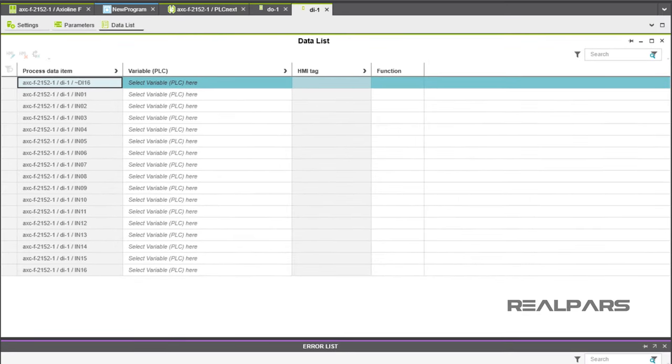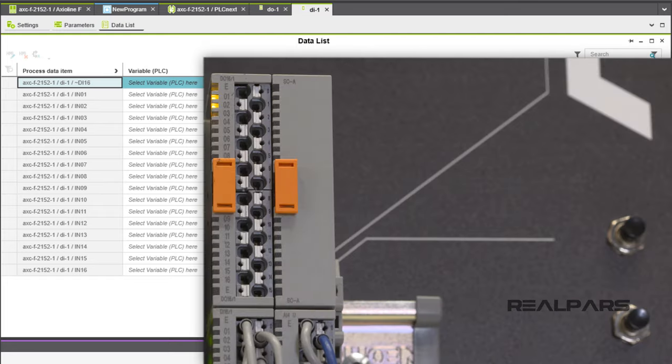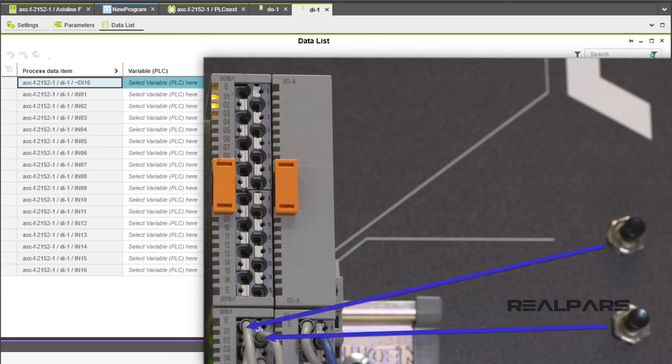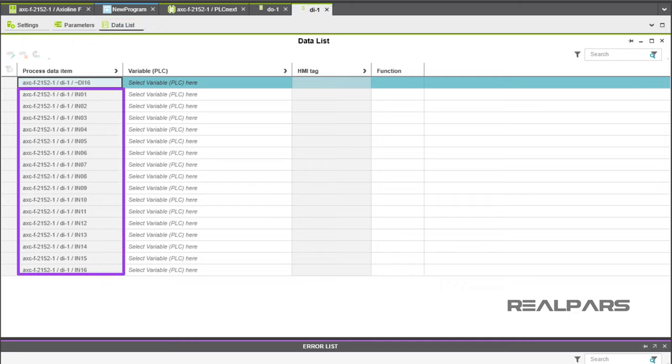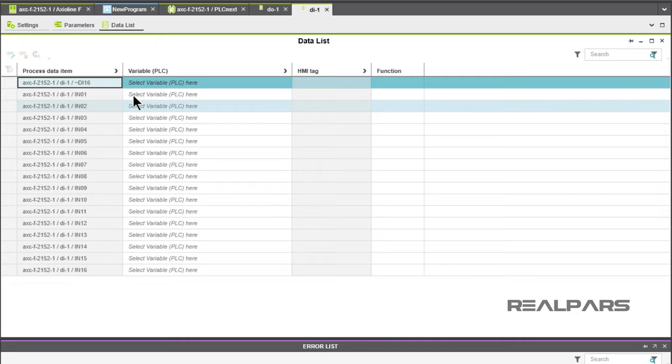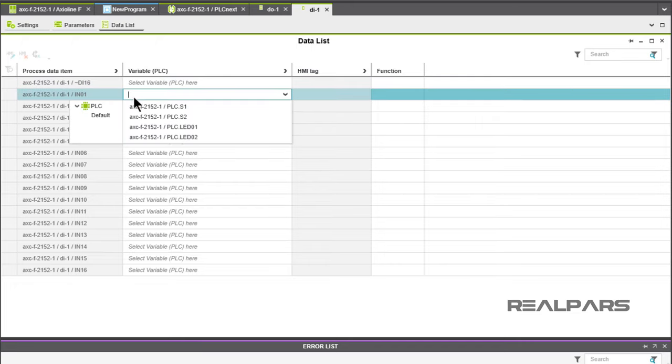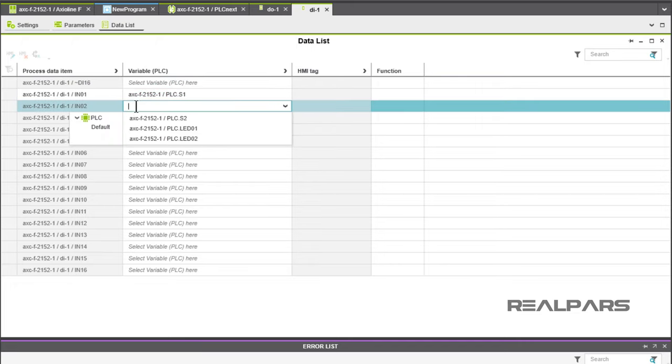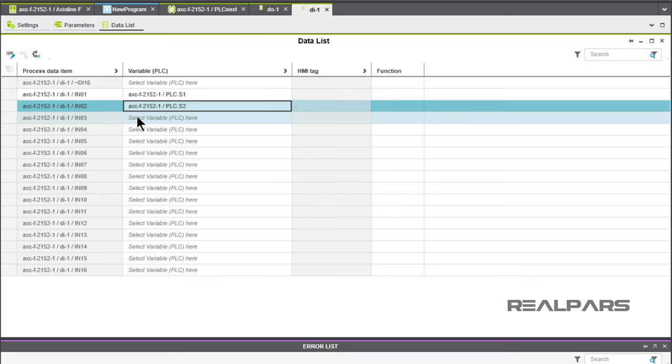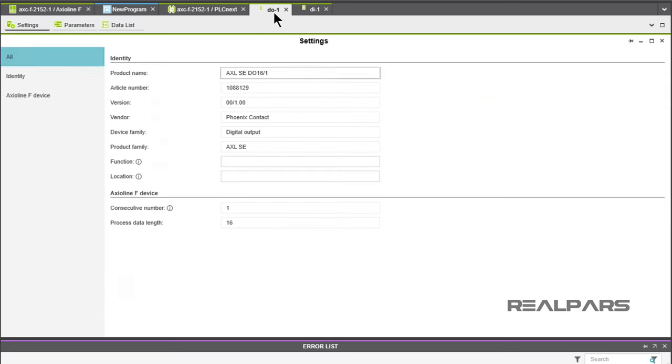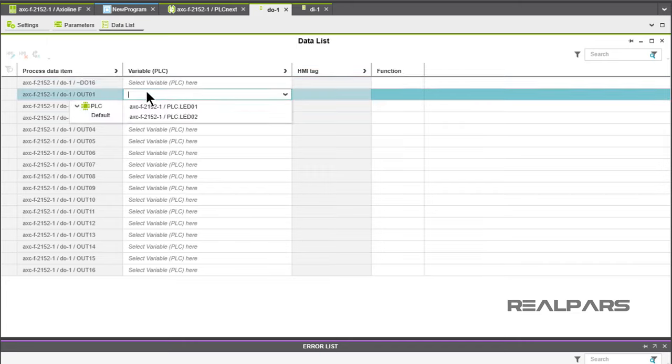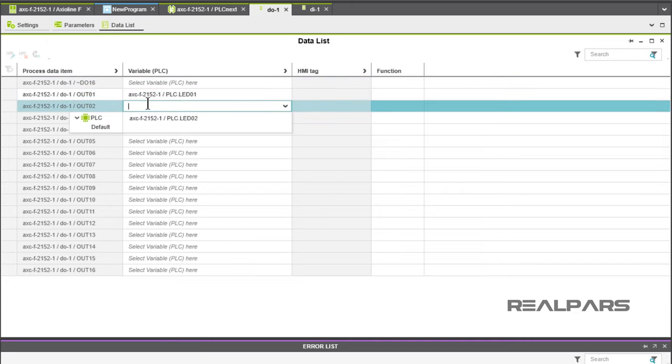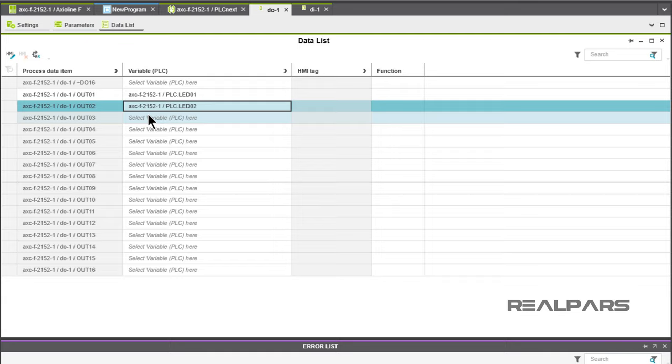Note that DI1 and DO1 now appear as icons at the top of the screen. Let's start with the inputs S1 and S2 that will be assigned to the Input Module in Slot 2. Choose Data List under the DI1 icon. All 16 unassigned inputs will be shown. We will assign S1 and S2 to Input 01 and Input 02 respectively. We will repeat the process for the outputs LED01 and LED02 and assign them to the Output Module in Slot 1.